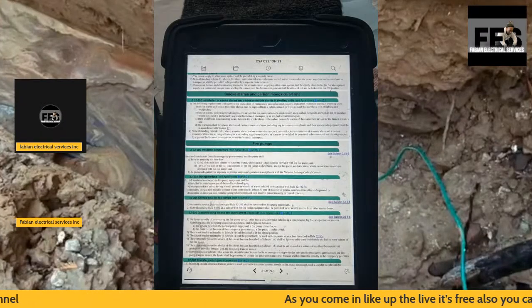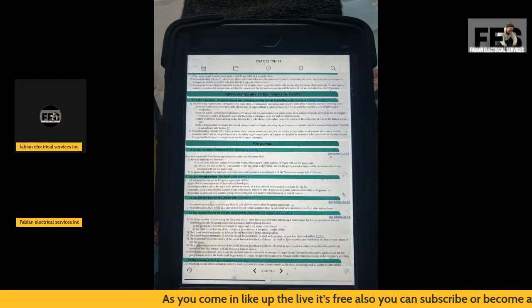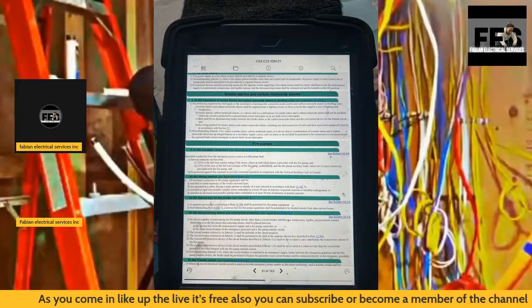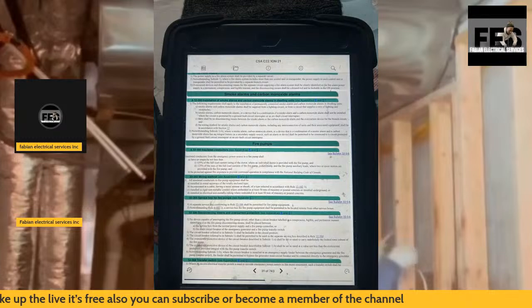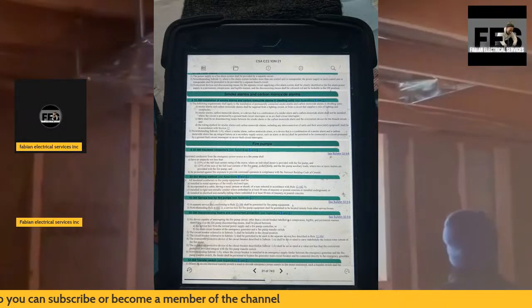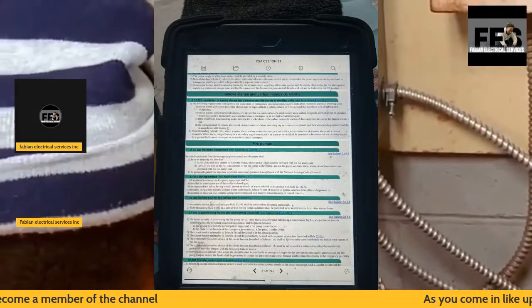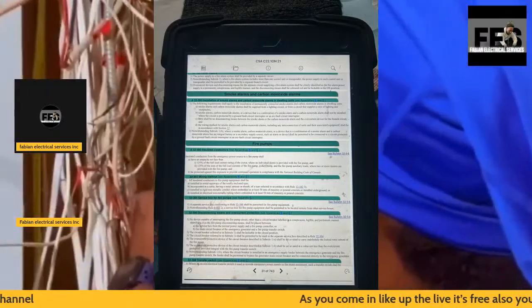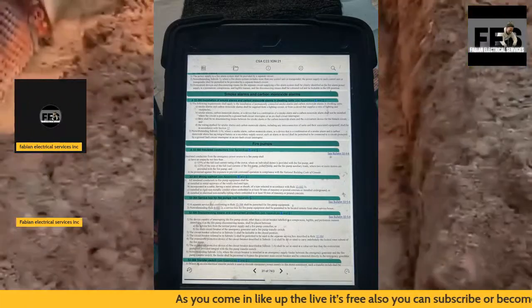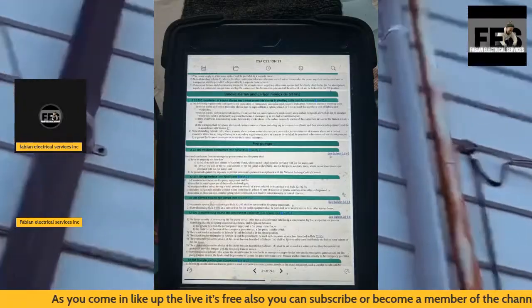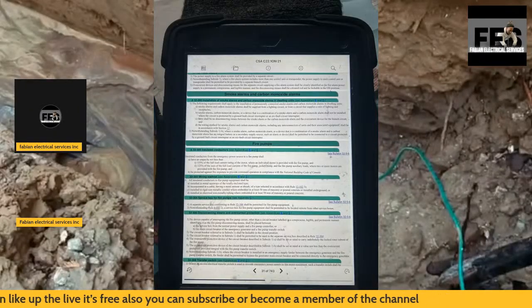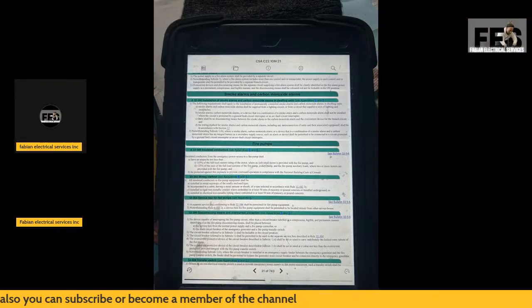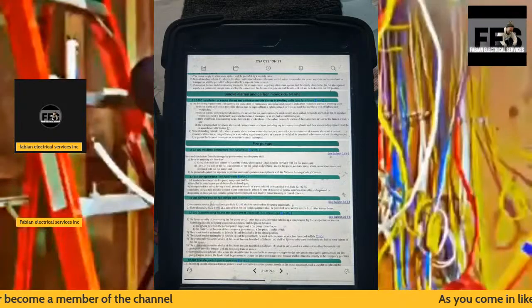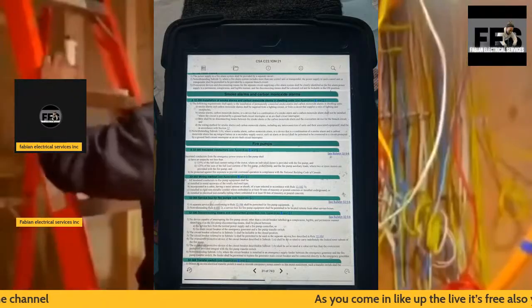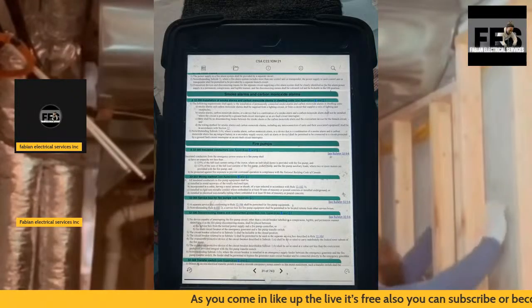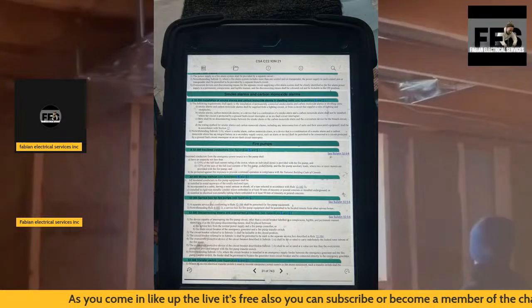Again, if the actual cable is run inside the attic and you need to walk up inside the attic, you have to make sure those cables are supported well. You're not walking on the actual wires themselves. That's why in the Ontario Electrical Code 2024, these rules are there where you have to place a 2x4 in order to protect those wires from being damaged or someone being hurt.